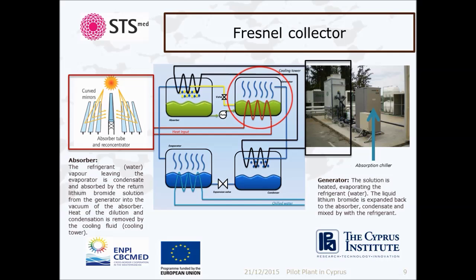We can see here 3 different loops. First, the chilled water. The chilled water is the liquid from which heat has to be removed. So usually the inlet is 12 degrees and the outlet 7 degrees for the Cyprus Institute. It's the liquid which is providing cooling to the building. The cooling tower system permits to condensate the refrigerant to remove the heat from the chilled water.